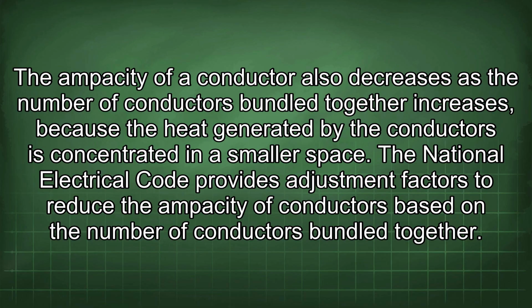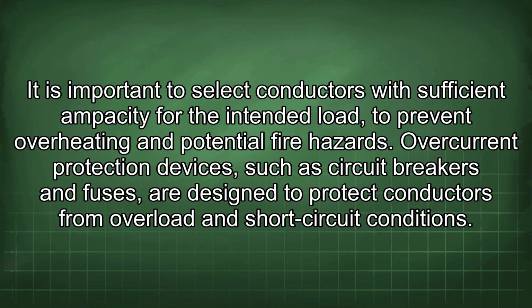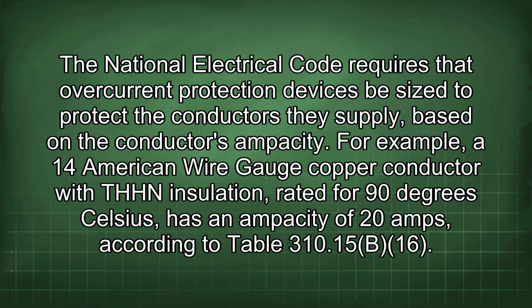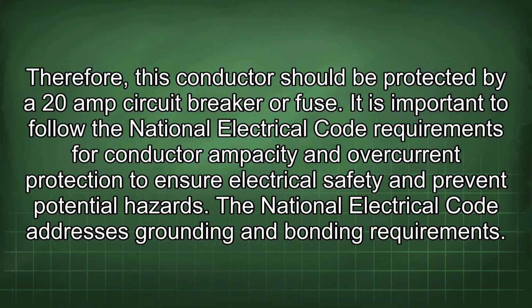The National Electrical Code provides adjustment factors to reduce the ampacity of conductors based on the number of conductors bundled together. It is important to select conductors with sufficient ampacity for the intended load to prevent overheating and potential fire hazards. Overcurrent protection devices such as circuit breakers and fuses are designed to protect conductors from overload and short-circuit conditions. The National Electrical Code requires that overcurrent protection devices be sized to protect the conductors they supply, based on the conductor's ampacity. For example, a 14 American wire gauge copper conductor with THHN insulation, rated for 90 degrees Celsius, has an ampacity of 20 amps according to Table 310.15(B)(16). Therefore, this conductor should be protected by a 20 amp circuit breaker or fuse.